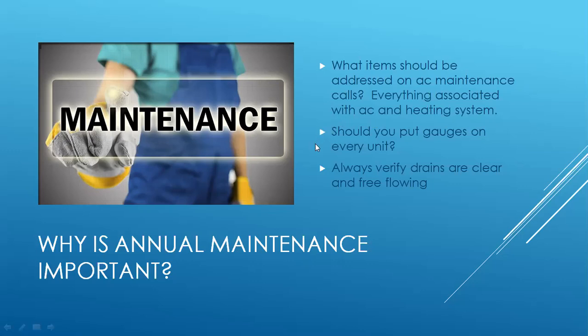Another big misconception is, I was taught this years ago, we put gauges on everything. It didn't matter what it was. You put gauges on everything. Now, through the years, people got smarter. You don't need to put gauges on everything. If I have two empty hoses and I go put gauges on it, Bob comes back in a month for whatever reason, puts gauges on it, or next year, then Tom comes. Well, pretty soon after 3 or 4 visits, because you're losing so many ounces every time you put hoses on there, all of a sudden the customer thinks they have a leak, and they don't. You were just losing refrigerant from putting gauges on and taking them back off. So don't put gauges on everything unless you think there's a problem.